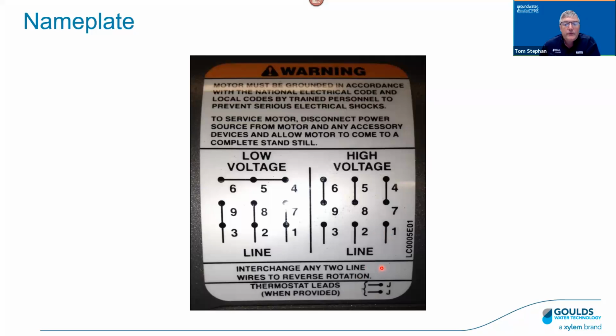The other piece of information we can see here is interchange any 2 line wires to reverse rotation. So this is 3-phase. So 3-phase can and will run backwards. And certainly we're talking about that connected to a pump, and the pump will actually give you some flow and some pressure, even if it's running backwards. So there's a little tip here saying interchange any 2 line wires for reverse rotation. Now what's different there with a drive is if you do have a drive or a VFD, you want to change any 2 leads on the output of the drive.